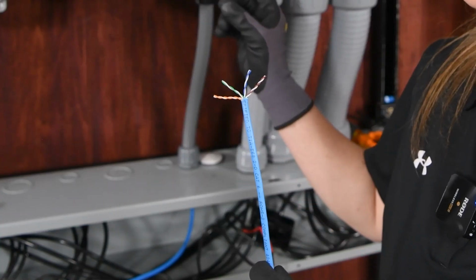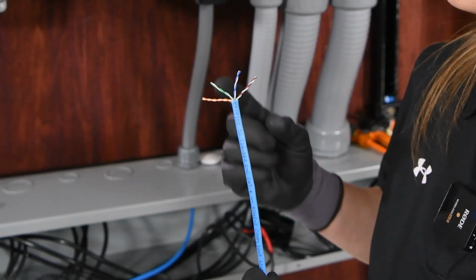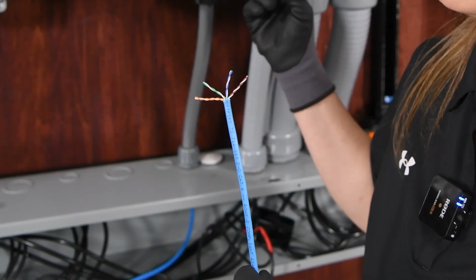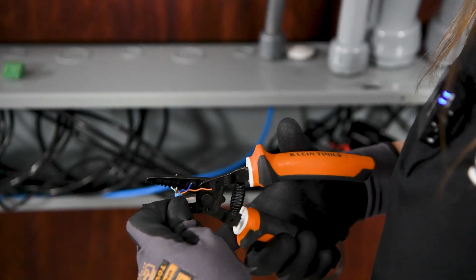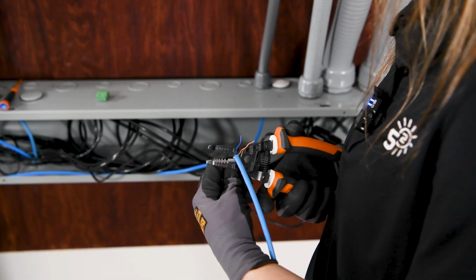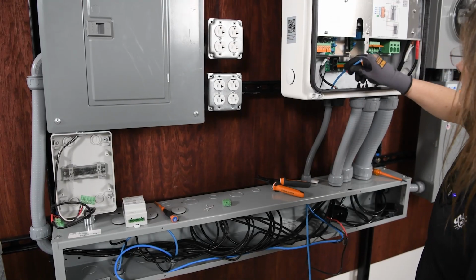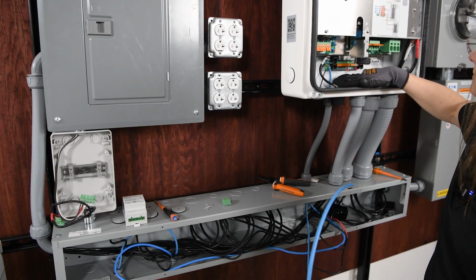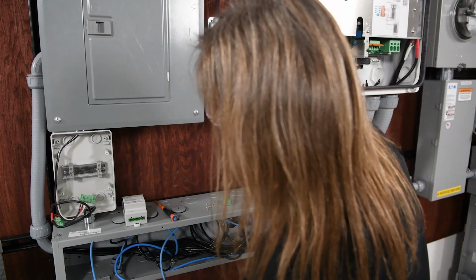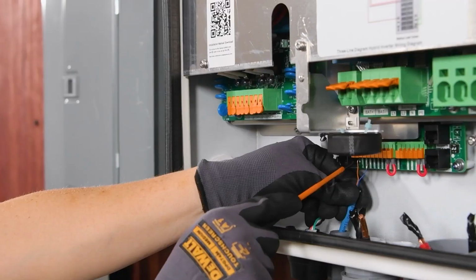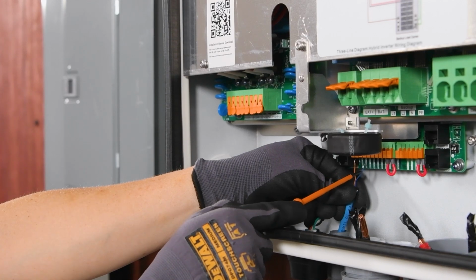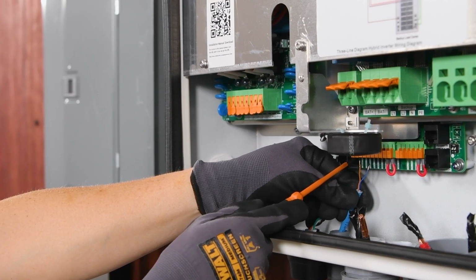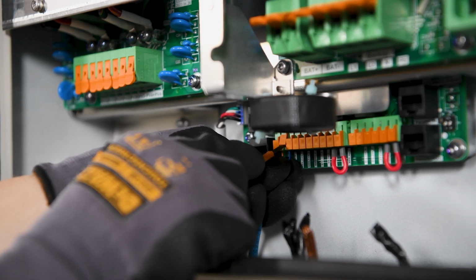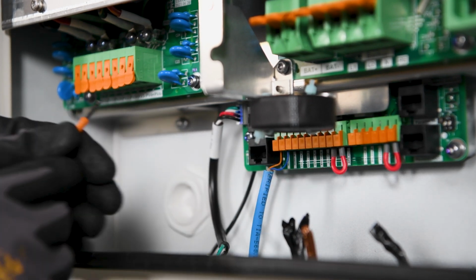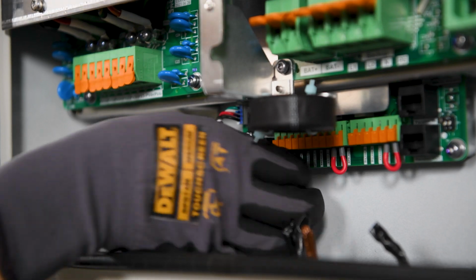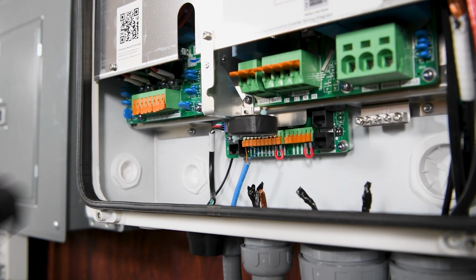If we use orange in A, we'll use orange in the Acrel meter, and if we use blue in B on the communications board in the inverter, we'll use blue in the Acrel meter. Now, if we are running this low voltage cable through a conduit or trough with our other high voltage wires, we'll need to use shielded wire with the same voltage rating as our other conductors. So we'll be inserting orange in A and blue in B. And to install these, we'll just insert an electrical screwdriver, push up on this orange tab, insert that into the hole, release, and then give a gentle tug to make sure that it grabs onto it.